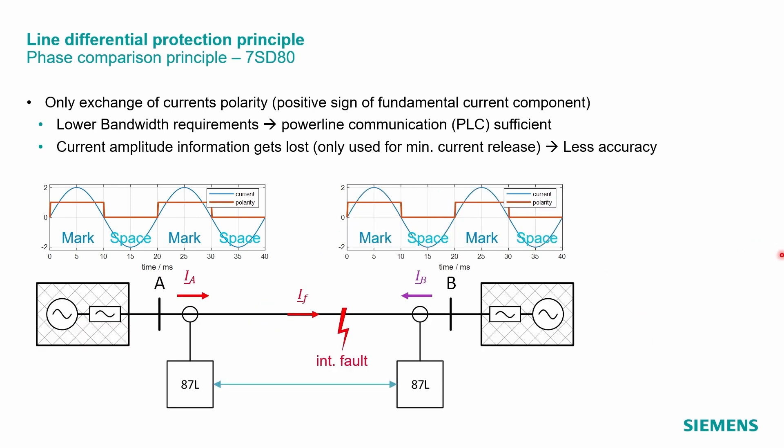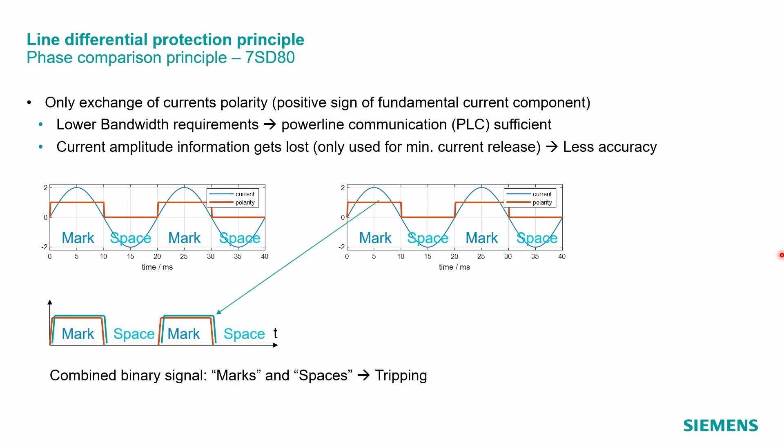For the internal fault condition, the currents at the line terminal A and B are more or less in phase. So both relays see the fault in the forward direction. The combined binary signal with local and remote current polarities result in a sequence of marks and spaces, shown here. This will result in a trip condition.